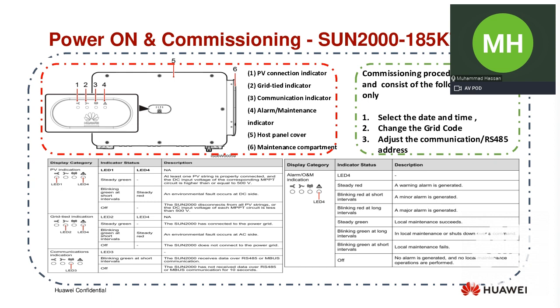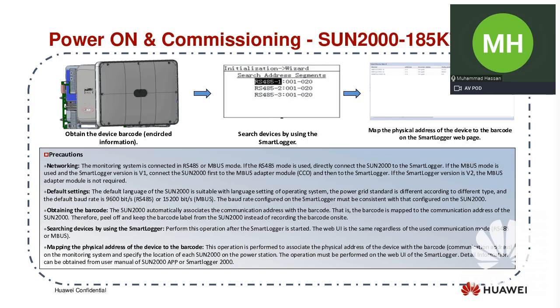For the commissioning procedure, you just need to select the date and time for that inverter. Then you select the appropriate grid code. It depends on the size of the site. For the UK, we have 4 types of G99 grid codes, so it depends on the site size or what is recommended by your DNO. So you need to select the grid code accordingly. The third step is to adjust the communication address or RS485 address so that the inverter will communicate with your communication equipment, Fusion Solar or whatever monitoring platform you are using. The important thing is that if you are using one inverter, that is not a problem.